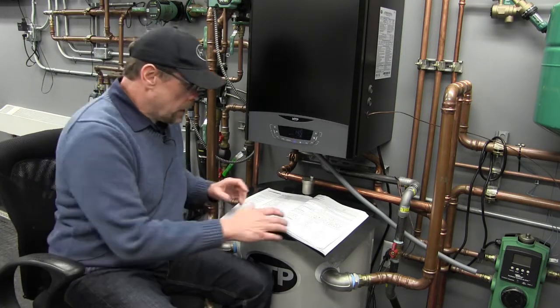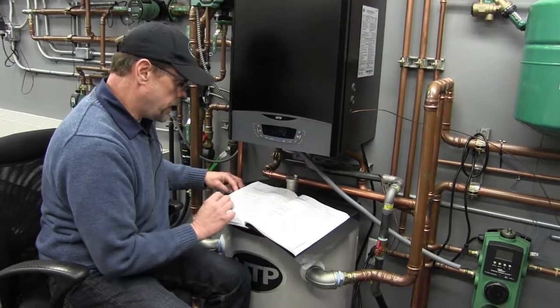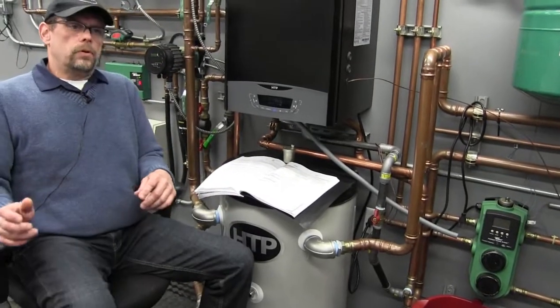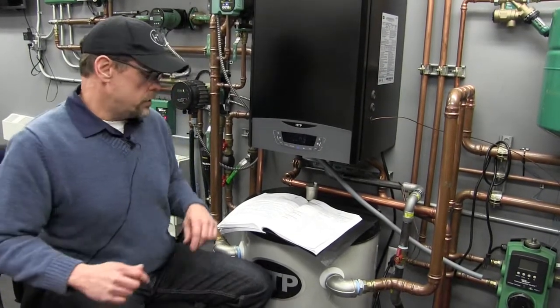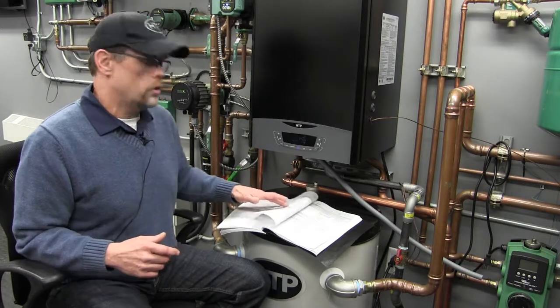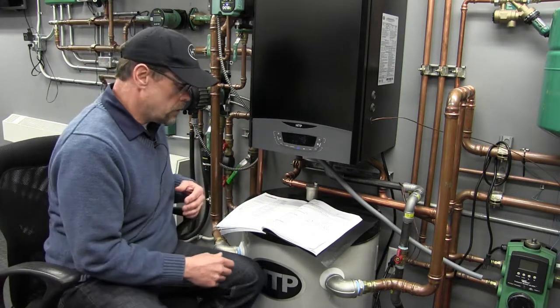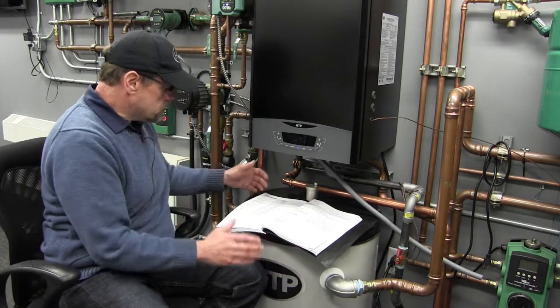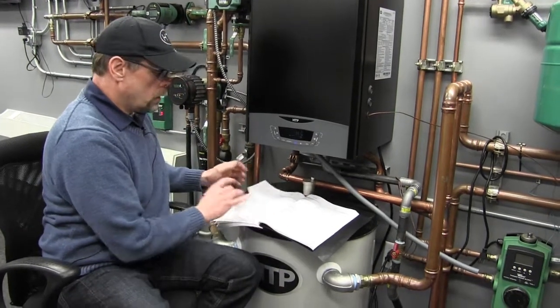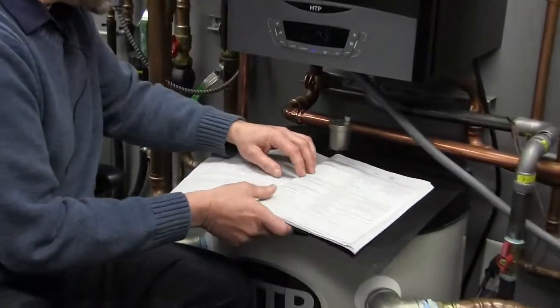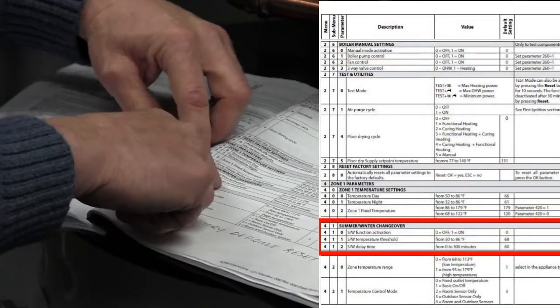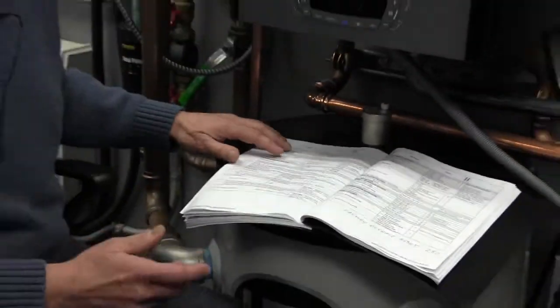However, let's take a look at the central heat parameters in the full menu because, for example, say we did the installation in a nursing home. Most factory default warm weather shutdowns are preset to 68 degrees, and anybody who works in nursing homes knows that can be a little aggressive. We might want to adjust that to 74 degrees before we shut the heat off. Because the quick access didn't address warm weather shutdown, only the minimum requirements, we go into our full menu, where we have the ability to change the outdoor reset or warm weather shutdown temperature.